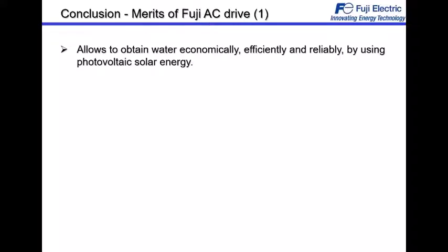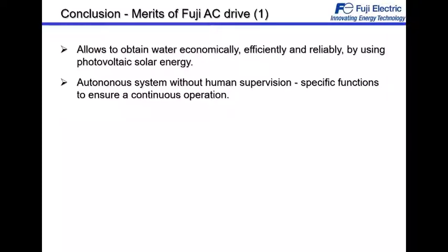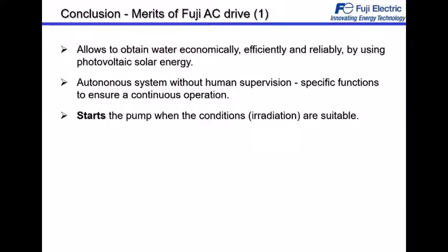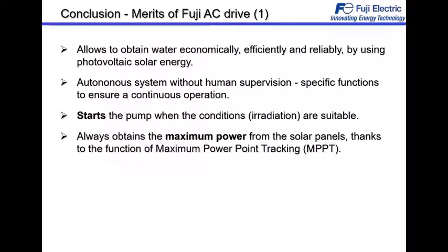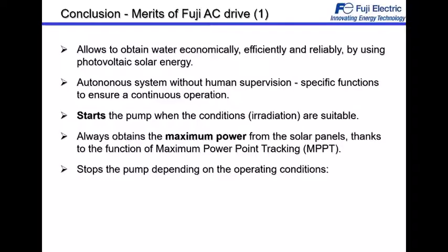So, some conclusions. Merits: it allows us to obtain water economically, efficiently, and reliably using photovoltaic solar energy. It's an autonomous system without human supervision, with specific functions embedded in the drive to ensure continuous operation. It starts the pump automatically when irradiation conditions are suitable, always obtains maximum power from the solar panels thanks to the MPPT function, and stops the pump depending on operating conditions.